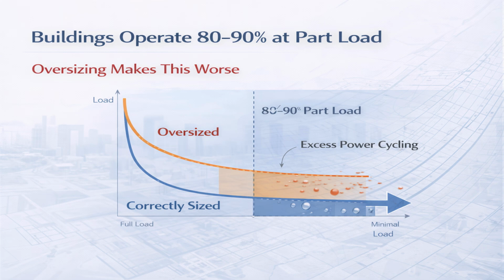Now compare that with a correctly sized 8TR unit. The unit runs longer and more stable cycles. It removes both heat and moisture effectively, temperature and humidity remain consistent, and the system operates closer to its designed efficiency range. This is why proper sizing improves comfort, reduces energy use, and extends equipment life. In HVAC design, oversizing does not create safety, it creates performance problems.